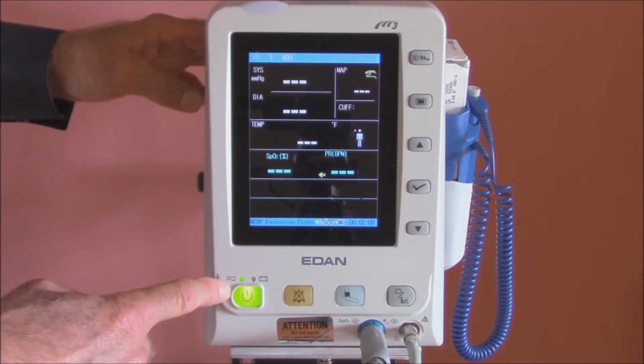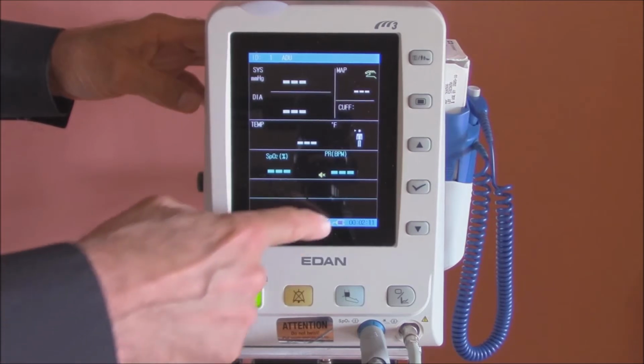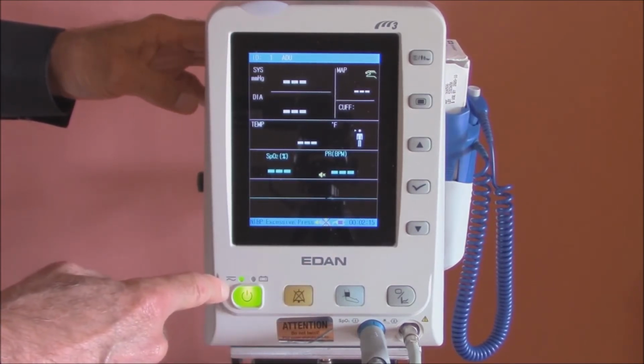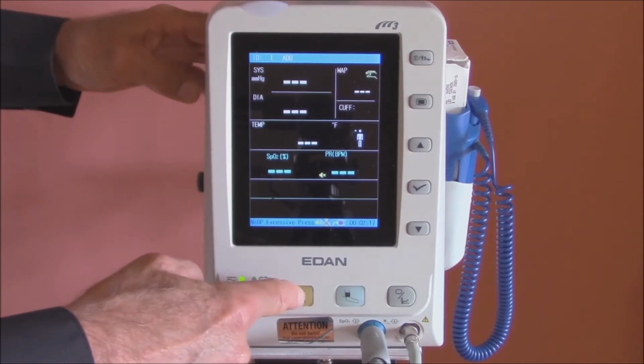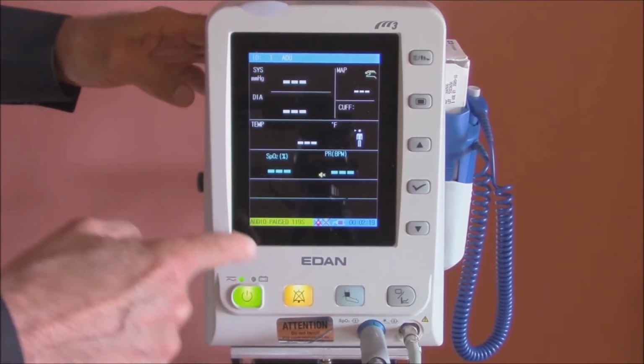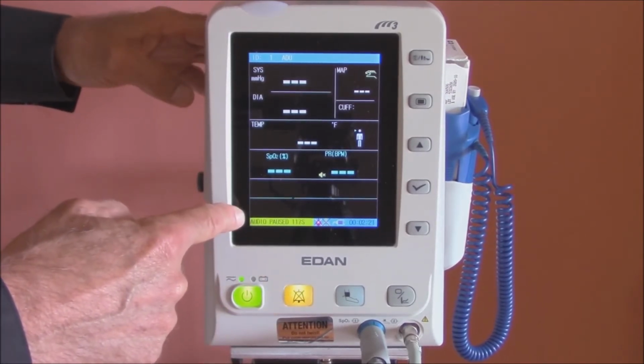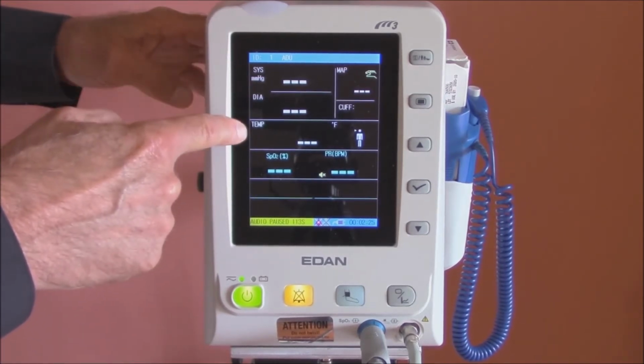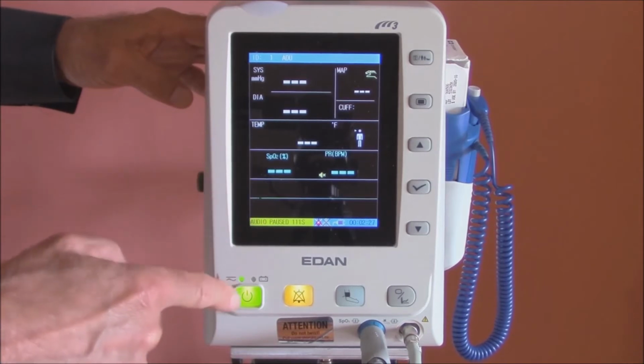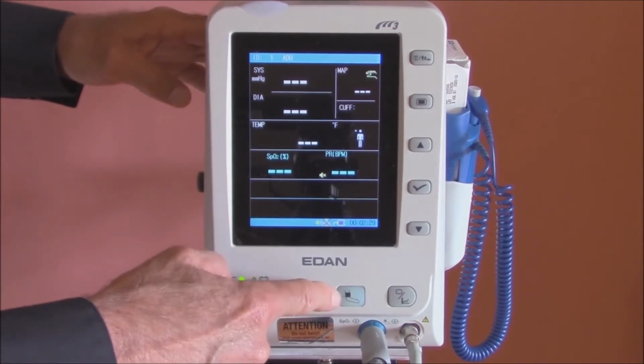It is best practice to have the Vitals cart plugged in and charging at all times when the cart is not in use. The next button is the silence button. This button will silence any medical alarms for 2 minutes. To permanently silence an alarm, the caregiver can either retake the vitals measurement that triggered the alarm or turn the system off and on. The third button is the blood pressure button.